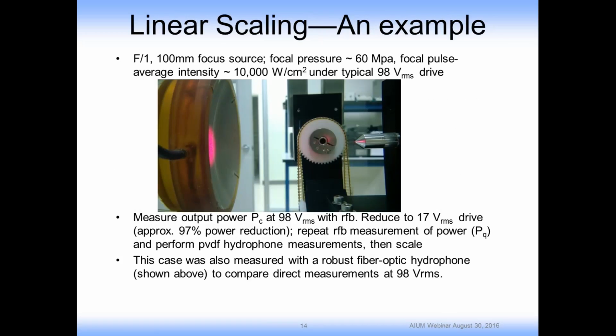So now I'm going to show an example of the use of these standards. I'll be talking about option 1, where we make measurements at the focus using the linear scaling. In this particular case, there was an F#1 transducer with a 100 millimeter focus. It's capable of focal pressures of 60 megapascals with pulse average intensities of 10,000 watts per centimeter squared under a typical 100 volt RMS drive. And that's what's shown here on the left.